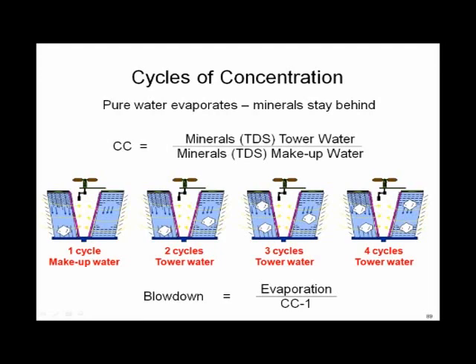So what I'd like to try to do here real quick is, if you've never really looked at cycles, help you understand what it is. Here's a formula for it. And it's based on the blowdown rate of the tower versus the evaporation rate. And if the blowdown rate is equal to the evaporation rate, you've got 2 cycles of concentration. So let's just walk through this real quick. You've got a formula, but see if you can understand a quick rock story of what cycles are, because you need to begin to think about this because the code for the first time is specifying the cycles of concentration on your cooling tower, and you're going to have to deal with this.